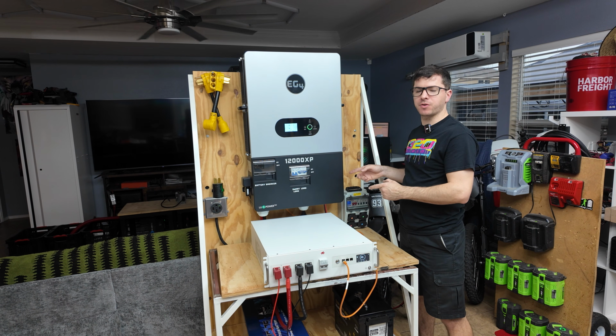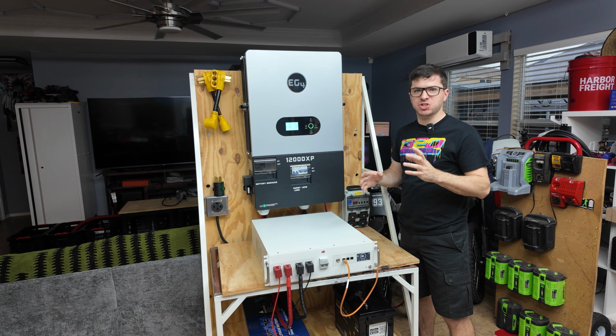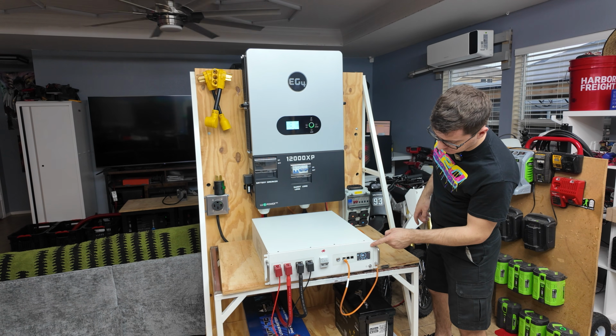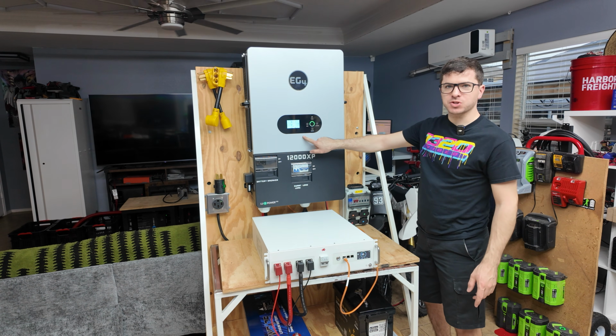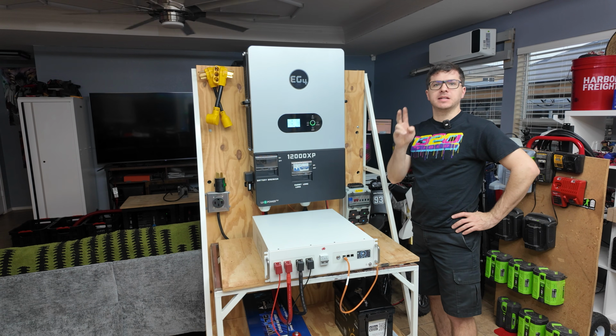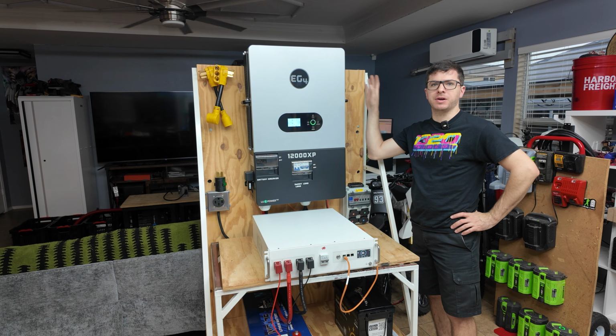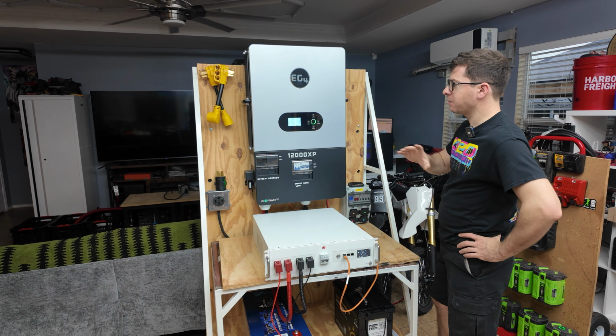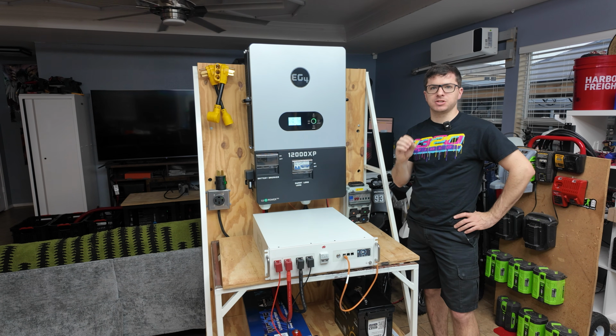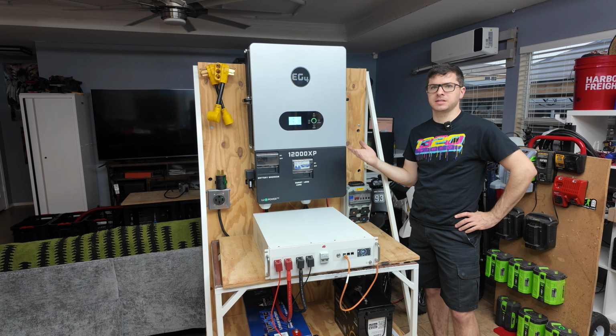We went ahead and turned the inverter on, and all I had to do to get communication working is make sure the battery was set to Pylon, which it was. In the EG4 software, select lithium battery and type 2. Type 2 is going to put the inverter in Pylon mode, and as soon as I did that, everything's working 100% just like it should—zero issues, zero fuss, literally as easy as it gets.